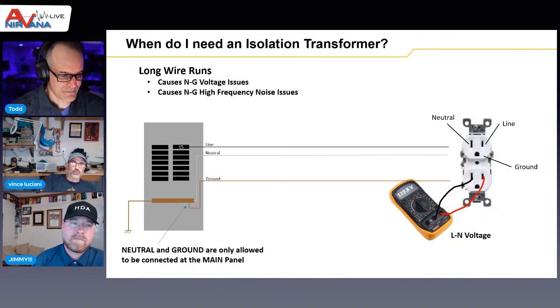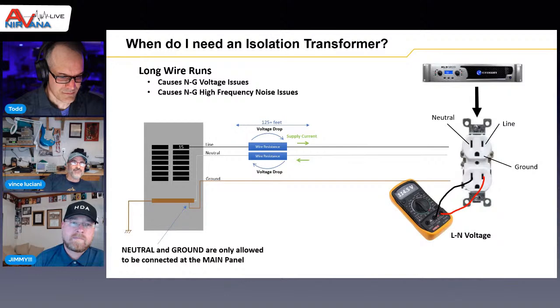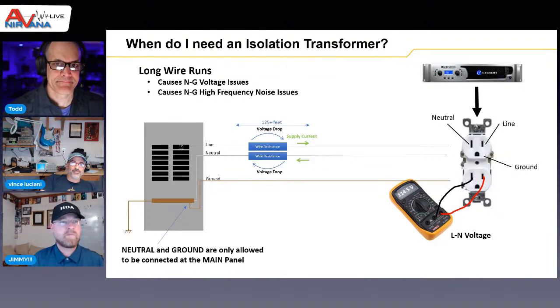In electrical terms, when you have two wires connected together, like neutral and ground, the voltage between them theoretically should be zero. But when you get really long wire runs, because your panel's on one side of the house and your theater's on the other, yes you'll put a dedicated 20 amp circuit for your AV system, but it's on a really long wire, and you'll get a voltage drop across it.